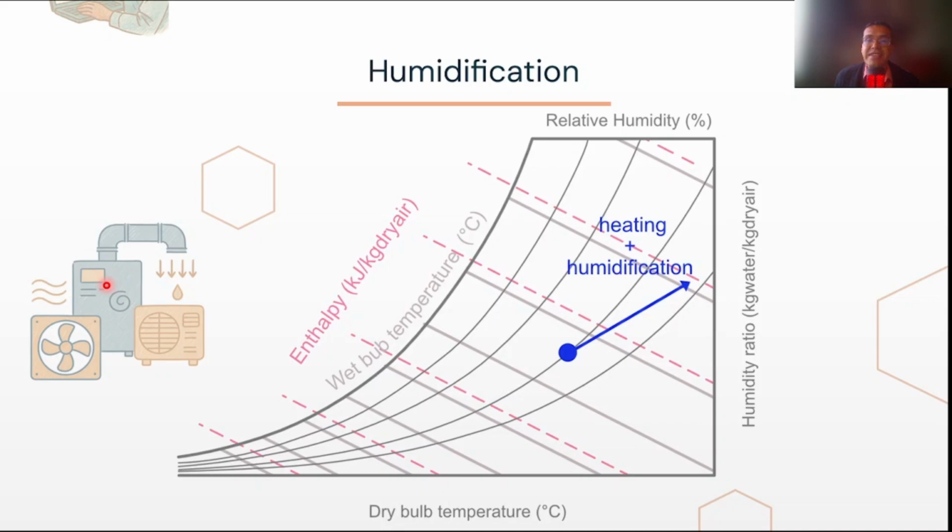Cooling the air while increasing its humidity can lead to discomfort, promote condensation on surfaces, and make climate control harder to manage. As a result, HVAC systems generally apply humidification during heating periods when adding both heat and moisture helps maintain comfort and indoor air quality. For example, during winter in a cold climate, adding moisture to heated air avoids dryness without overcooling the space.